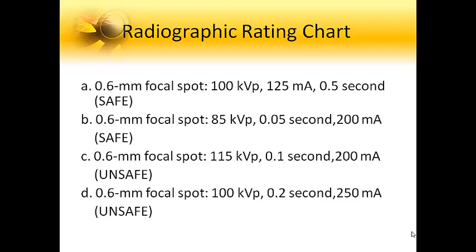If an unsafe exposure is made, then the tube might fail. However, nowadays X-ray systems have a microprocessor control that does not allow an unsafe exposure. So you don't need to worry about this.